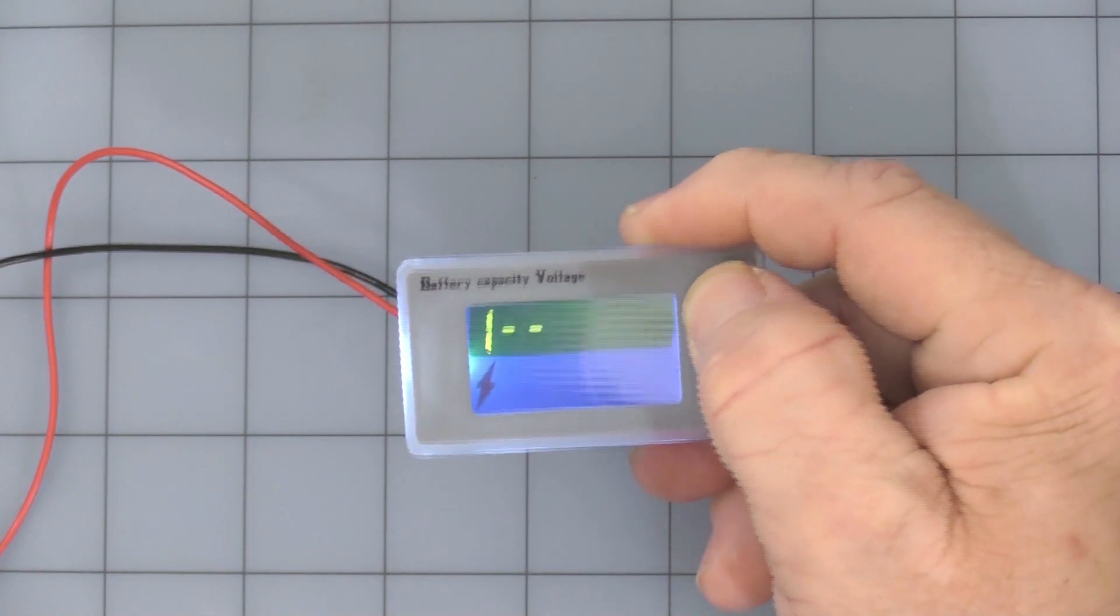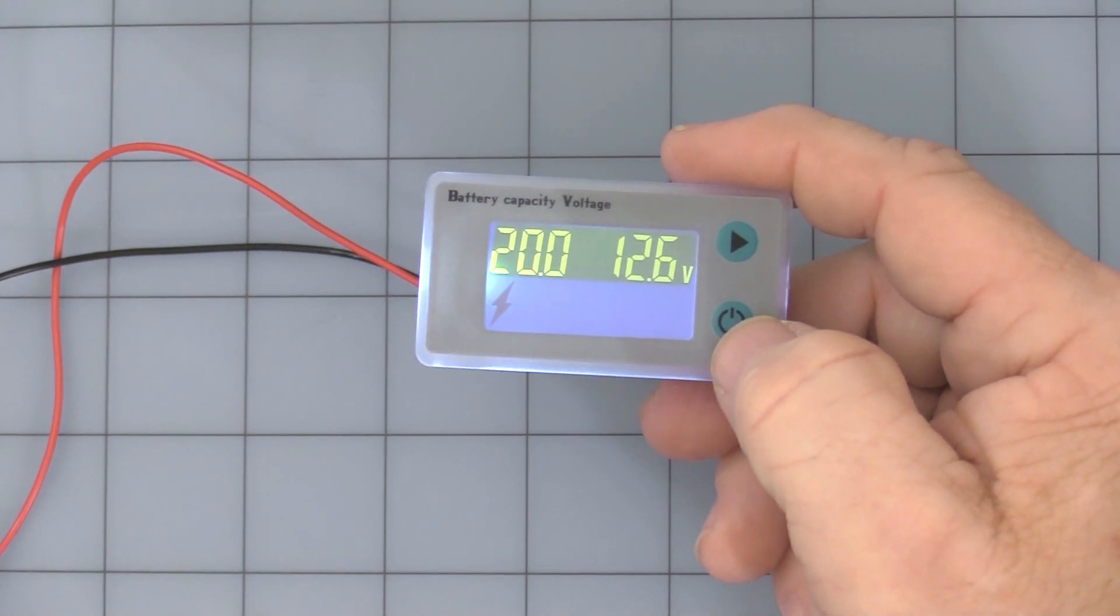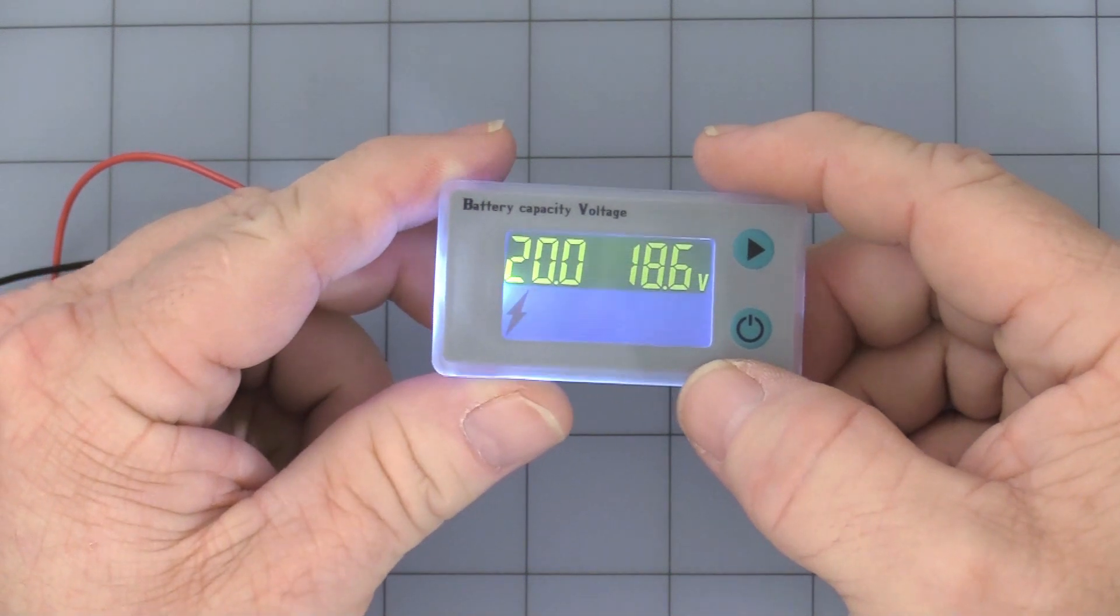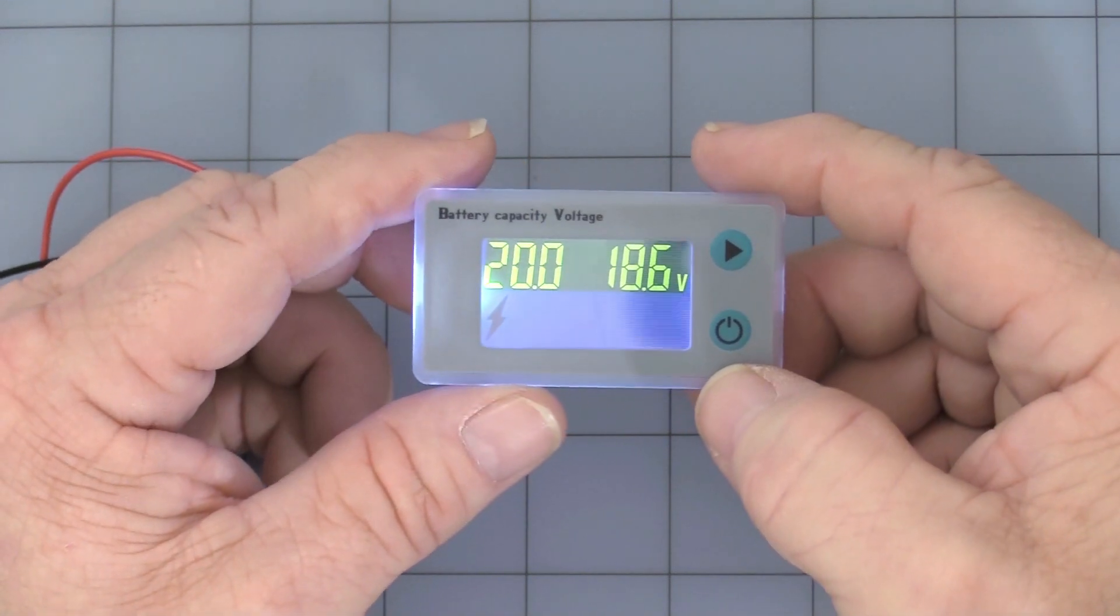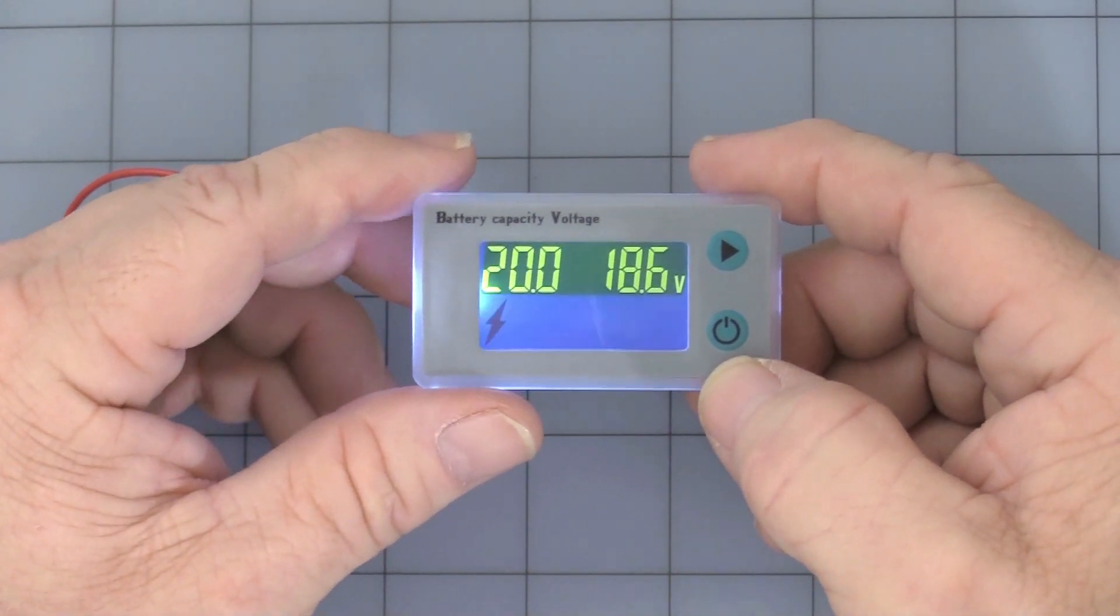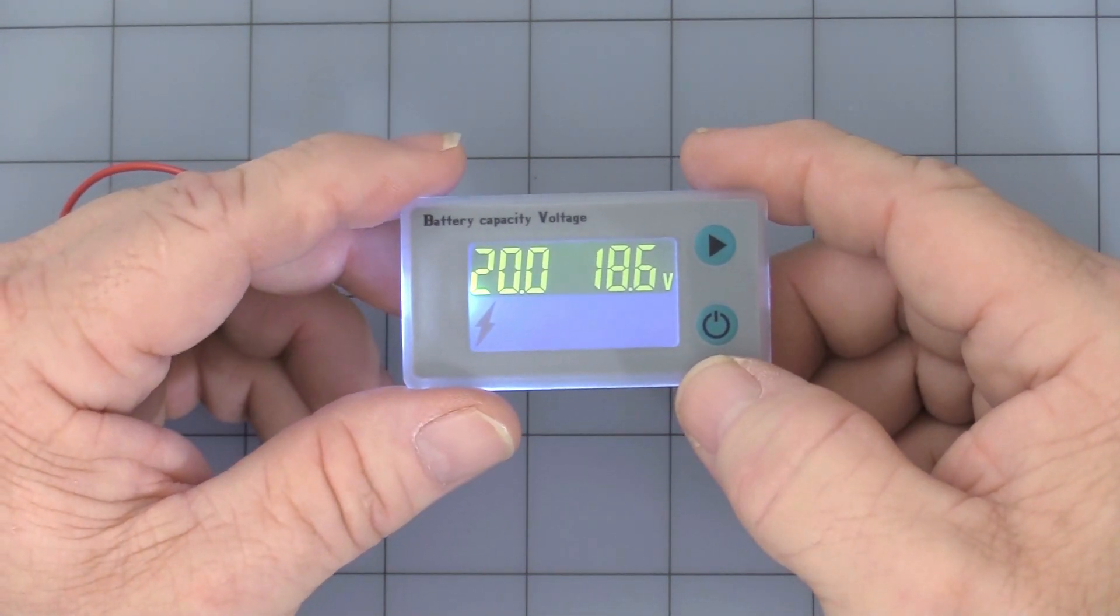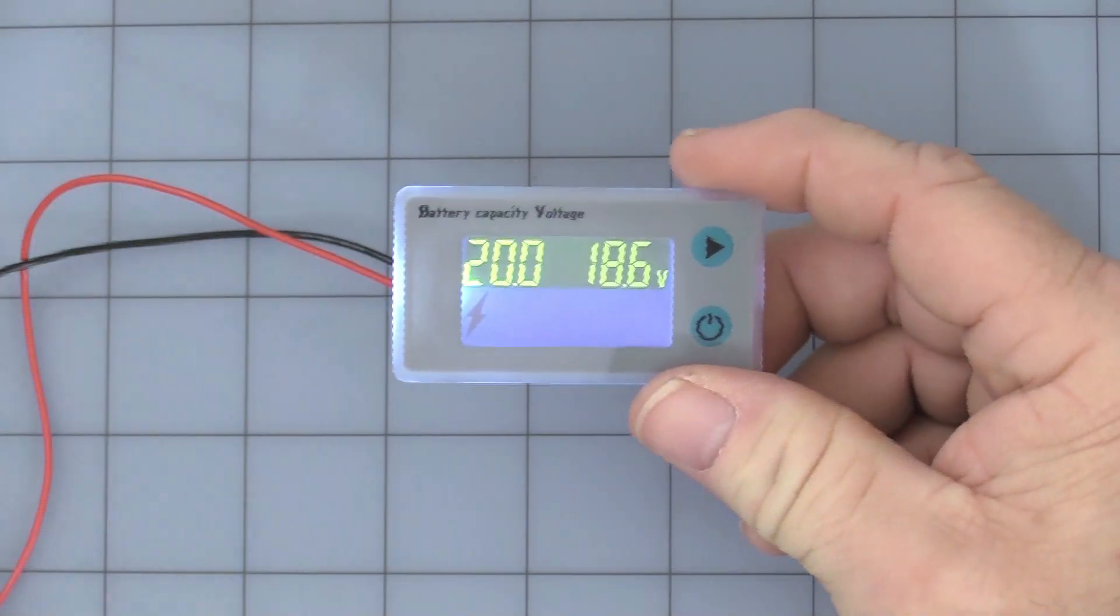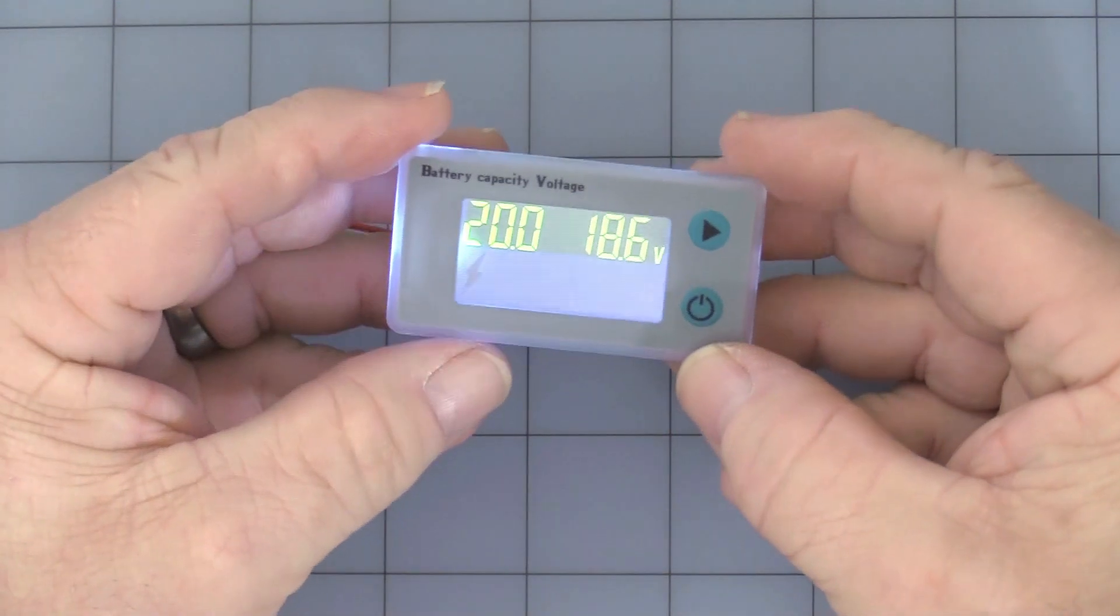That's it. One, two, three, four, five. Oops, I'm going to recalibrate this thing. See if I can escape before, see how long it takes. Well, essentially as you can see what happens if I do recalibrate it. Actually it won't let you, and I remember reading in the manual, if it's between 19 and 20 volts is where it'll allow you to recalibrate. So if you need to calibrate it outside one volt, it's not going to let you do it. So I guess that's something to keep in mind. And my little power supply here won't go above 18.6. So that is the main features of the meter.